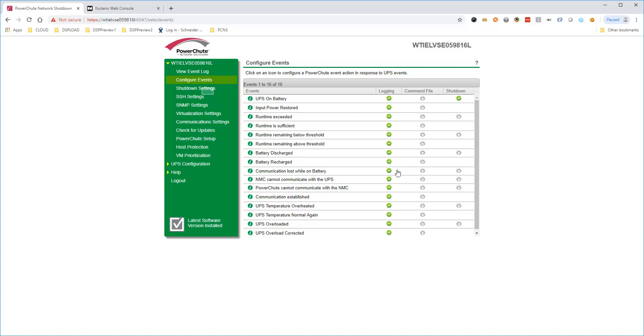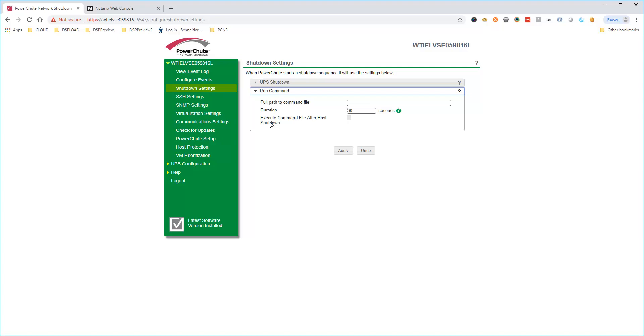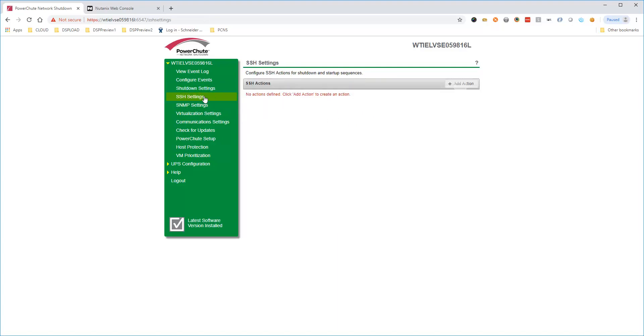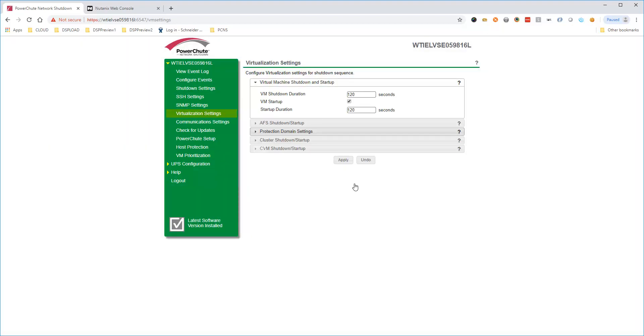Shutdown settings allows you to configure additional options when a shutdown occurs. Choose Run Command to configure a command file or script that could execute during the shutdown sequence. Choose if the command file runs before AHV hosts shutdown or after they have been powered down. From version 4.3, it is now possible to configure PowerChute to execute commands on remote systems via SSH actions. Multiple SSH actions can be configured by clicking the Add Action button. SSH credentials are encrypted and securely stored in PowerChute. Define multiple actions to run commands on several remote systems and define when each SSH action should be executed.